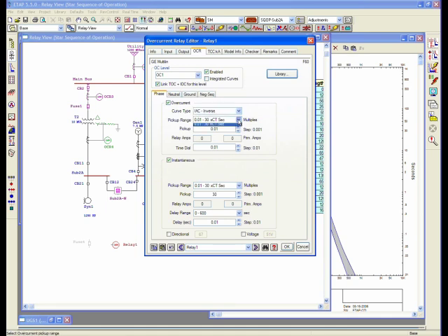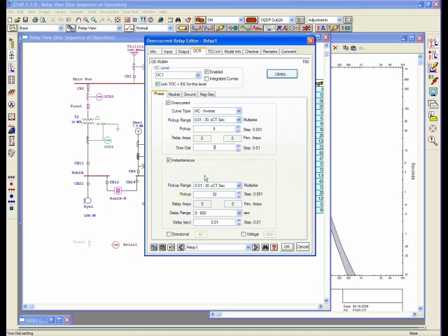The pickup ranges, the pickup value, which you can type in directly in here - let's say you type in 5, and a specific time dial within the range of that. And for the instantaneous, I'm going to go ahead and leave it as a time delay of 0.02.